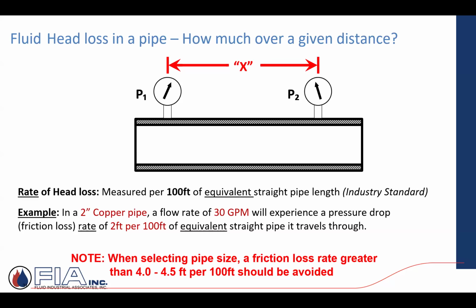As a rule of thumb, and as soon as you make rules of thumb, things can change. But when selecting pipe sizes, friction loss typically shouldn't be greater than around 4 to 5 feet per 100 feet, especially in closed loop heating and cooling in dormitories, office spaces, hospitals, places where noise can be a consideration. When you're in commercial manufacturing, maybe even pharmaceutical, maybe that 4 to 5 feet can be expanded.